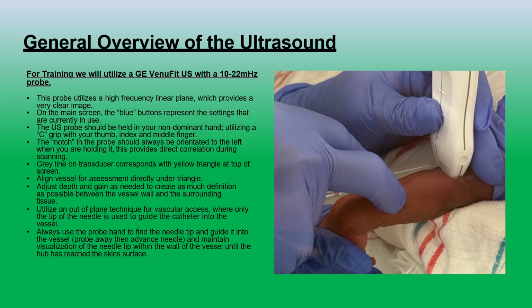There are some other settings on the ultrasound that we can go over once you actually start practicing. The two main things that we use are called depth and gain. Depth is pretty self-explanatory. Obviously, I can adjust how deep the probe is going to scan into the extremity. Typically, for probably about 90% of patients, we use a depth of 0.8 centimeters, so almost a whole centimeter down. That's usually plenty deep enough to show us, particularly if we're working in the periphery, plenty of vessels. We're going to see pretty much all the way through the arm or the leg at 1 centimeter for most of our smaller patients.